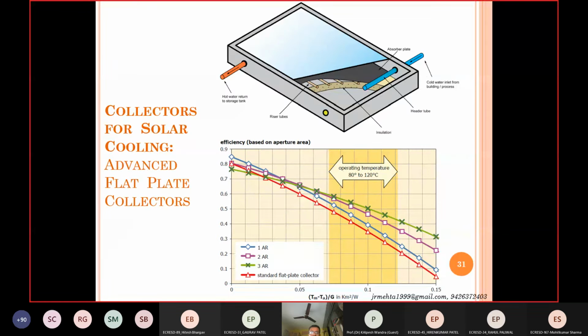So this is showing a solar flat plate collector, right? But an improved one, higher efficiency one as compared to the regular solar water heater, because for firing your air conditioning systems, you need generally higher temperatures. Okay, so if the operating temperatures are a bit high, in that case, even if you're using a flat plate collector, it should be of a better quality, as it is shown here.